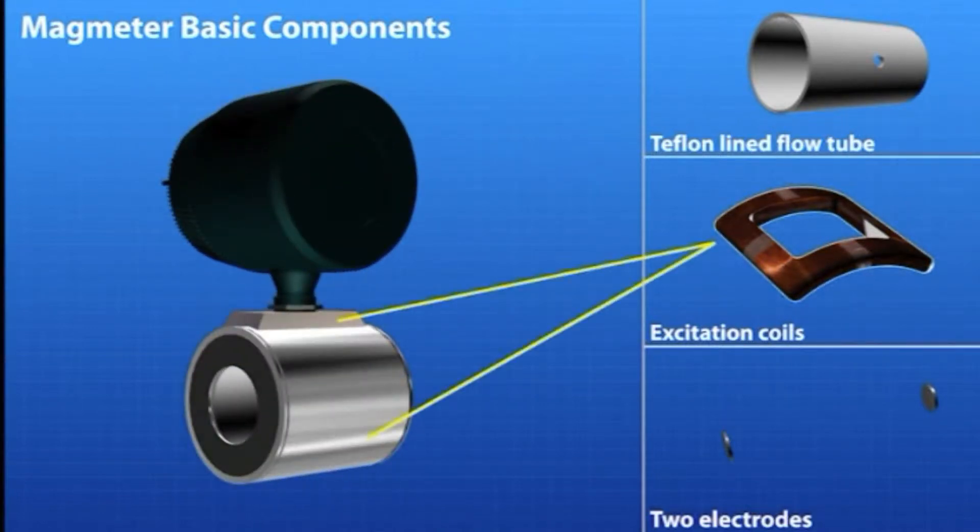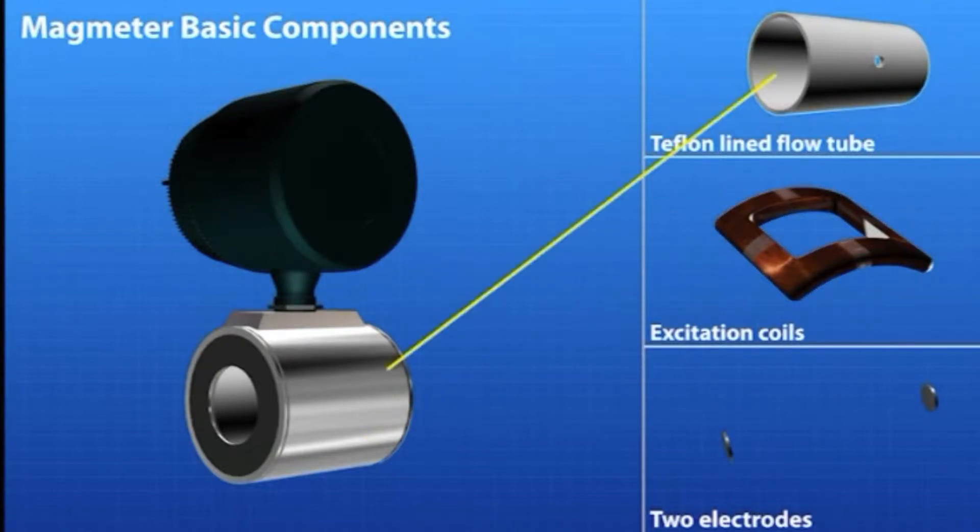Current is applied to the coils in the magmeter to generate a magnetic field within the flow tube. As a conductive fluid flows through the meter, an electromotive force is generated. This force is detected by the electrodes and the resulting value is converted to flow rate.